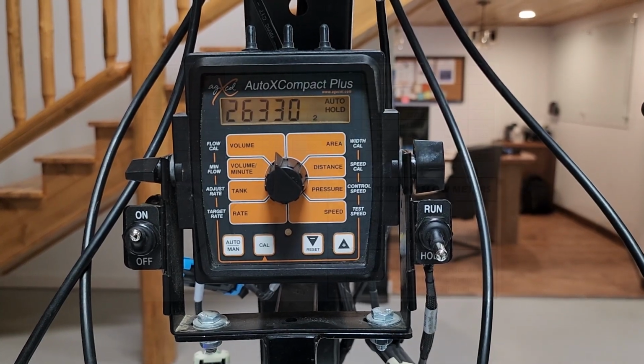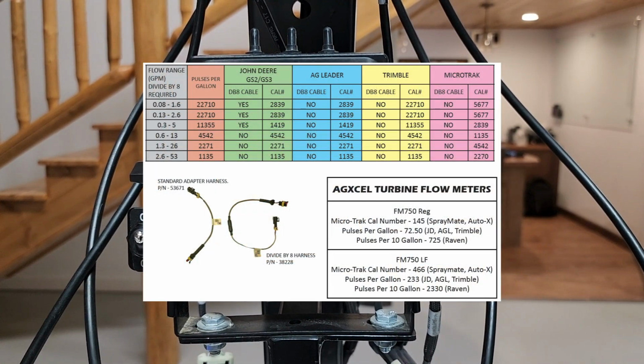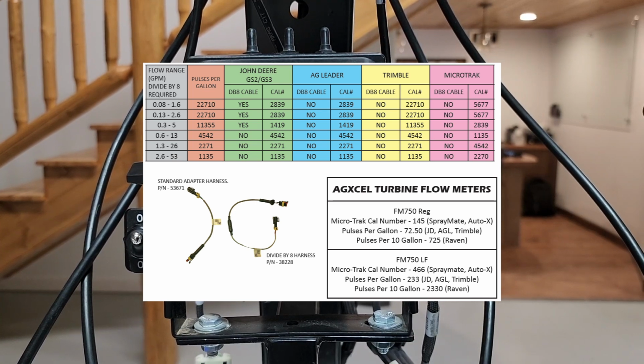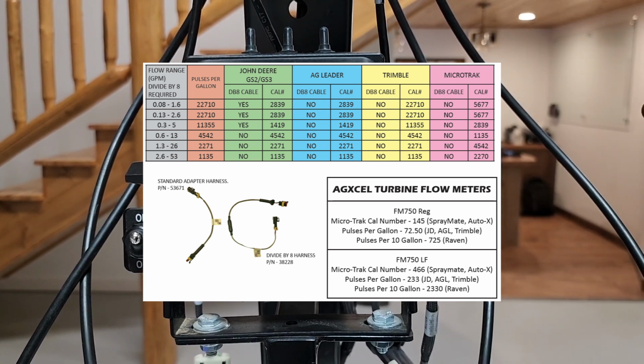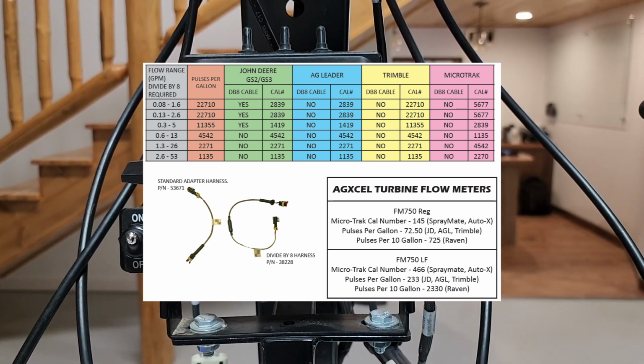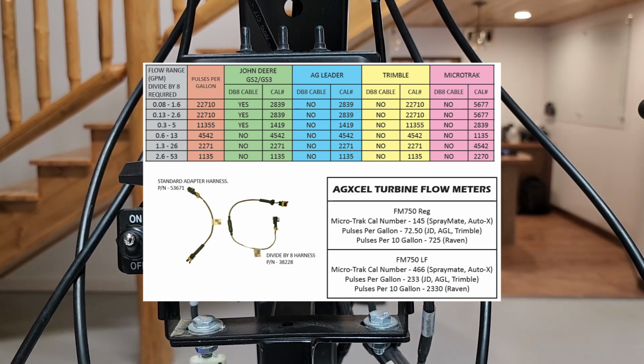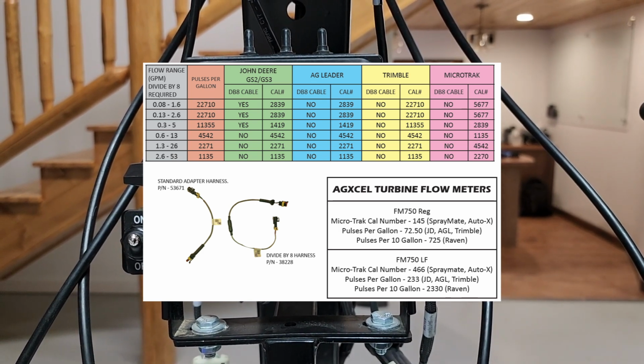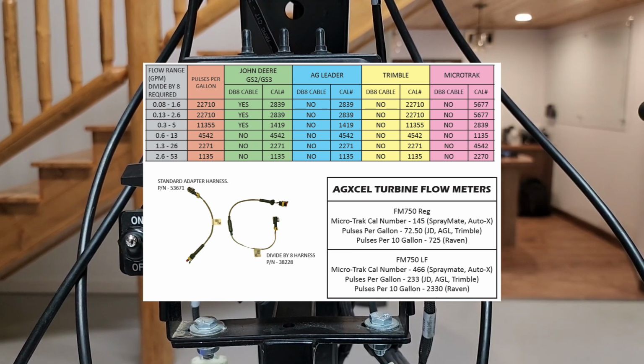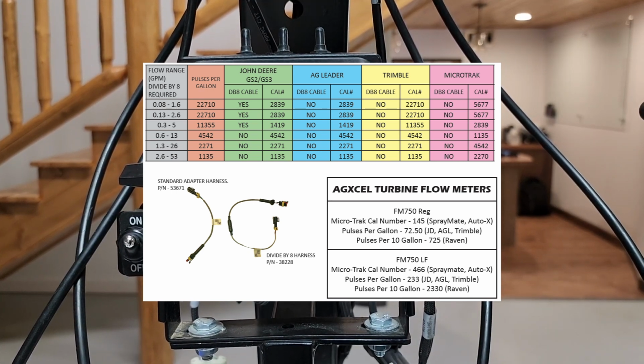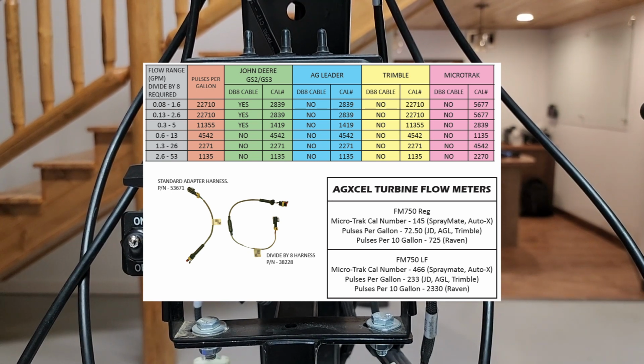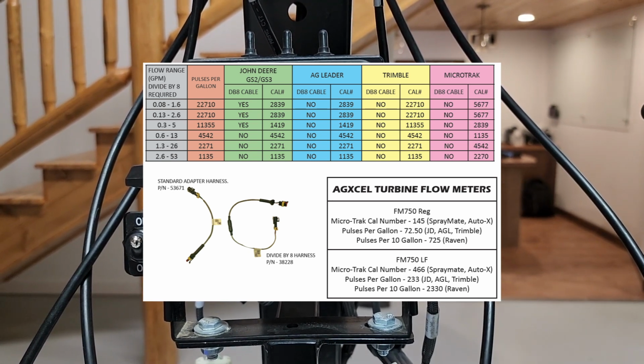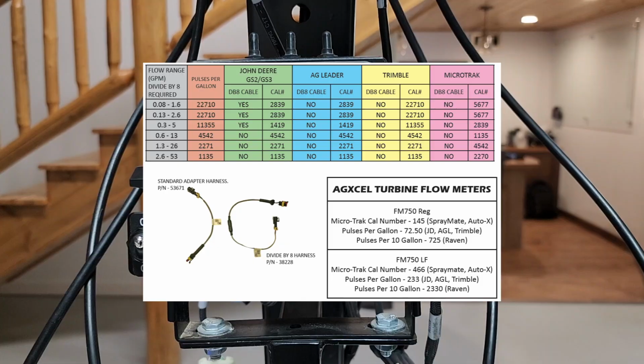And on screen now will be a list of the calibration numbers you have. Make sure again you check on the side of the flow meter, see what size flow meter you have, see what your pulses per gallon is, compare it to the chart, see if you need the divide by 8 cable or not. If so, make sure you see that in your chart that you're looking at and put that number in appropriately. If you don't need it, then go ahead and just put in your pulses per gallon as seen on your flow meter and on this chart.